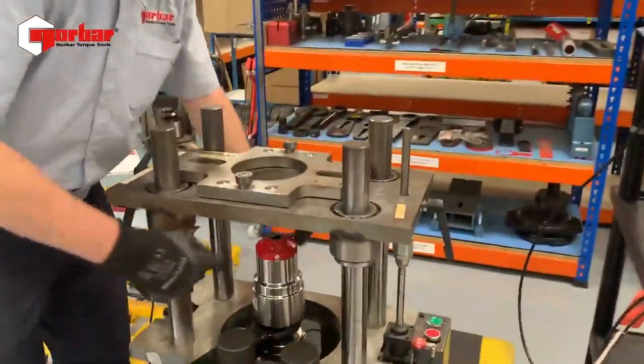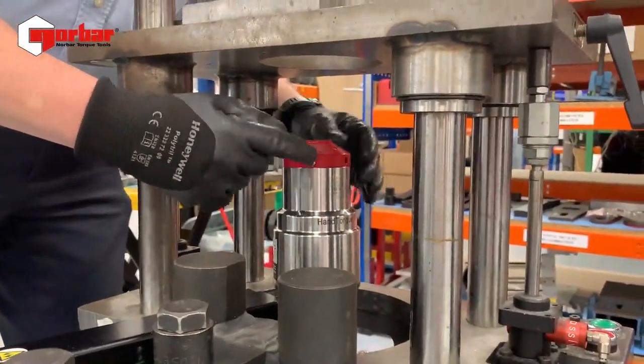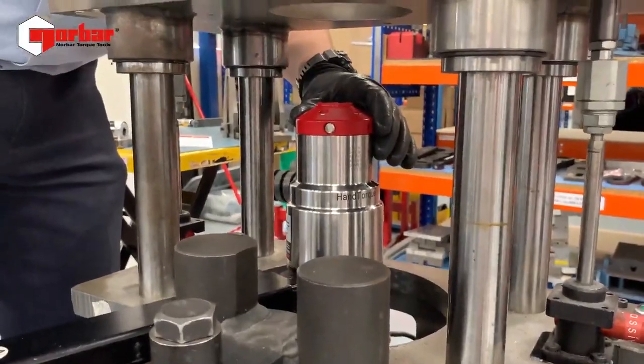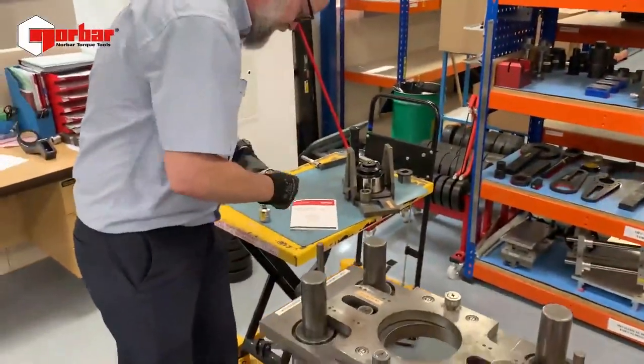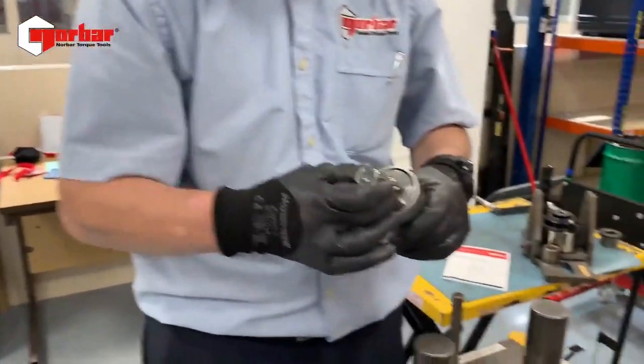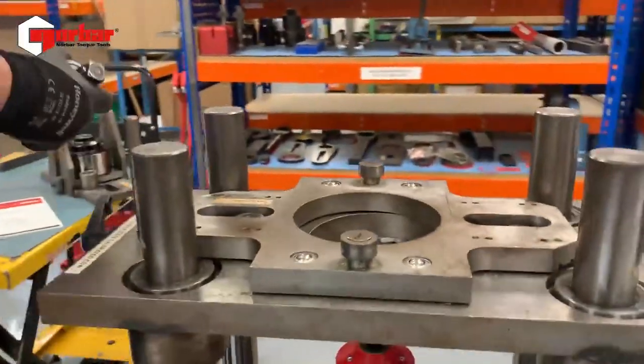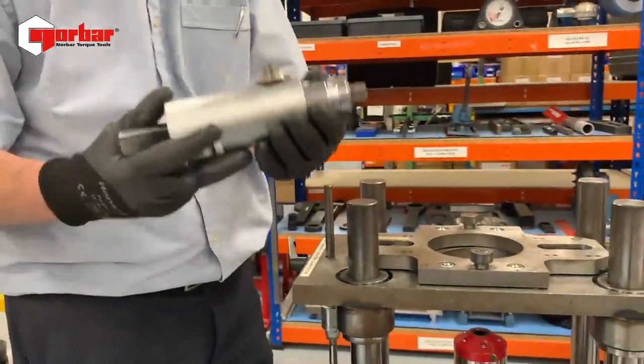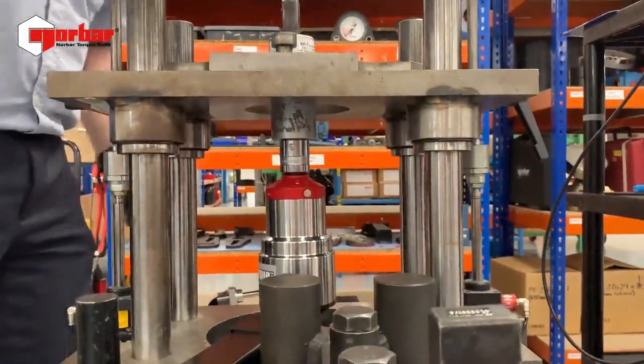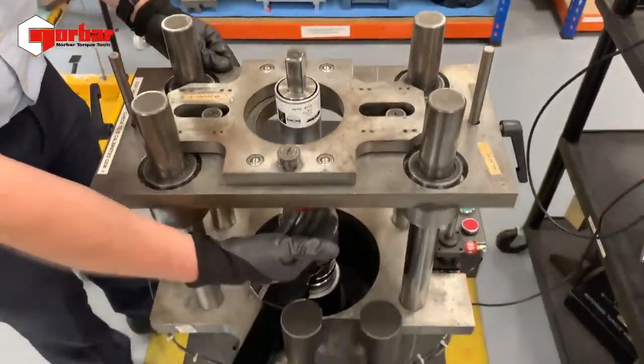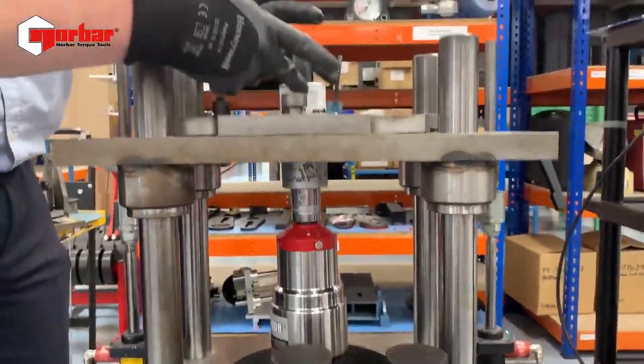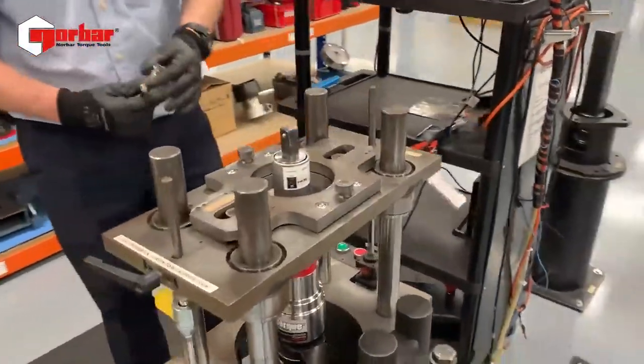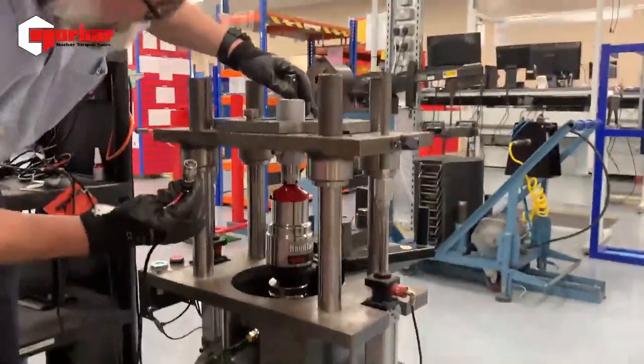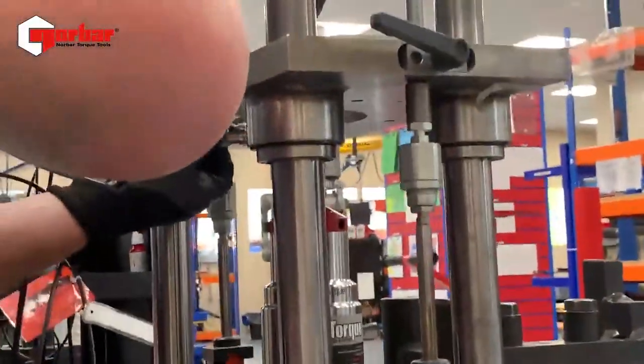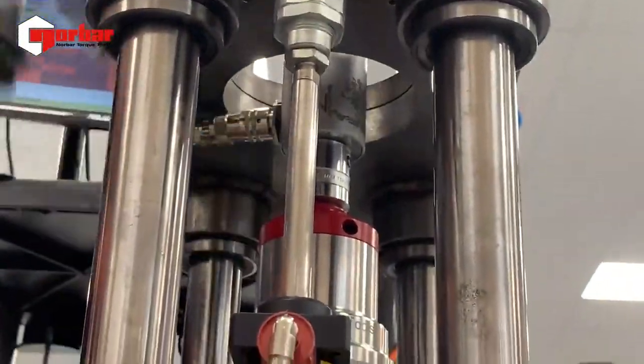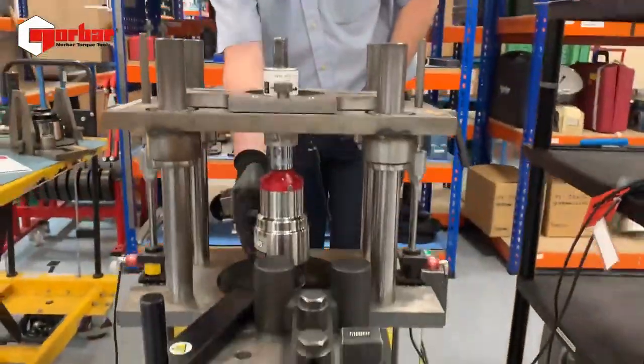We just need to ensure that if you've got an anti-wind-up mechanism installed, we're working in the clockwise direction. We've pushed our anti-wind-up bar to allow the clockwise direction to be functional. Okay, second piece, we're going to use a 3/4 to 3/4 male, drop into the transducer. A 3/4 to 1/2 inch. Okay, so we can now drop this assembly into our HandTorque. So we've now got output transducer, HandTorque installed with the appropriate reaction, input transducer. We're now going to connect our input drive transducer. So again, taking our transducer lead to the TTT, we're going to feed that in. Given the location of the transducers, it can sometimes be a little bit troublesome, but there we are, we're in place. So we've got input transducer, HT, output transducer.